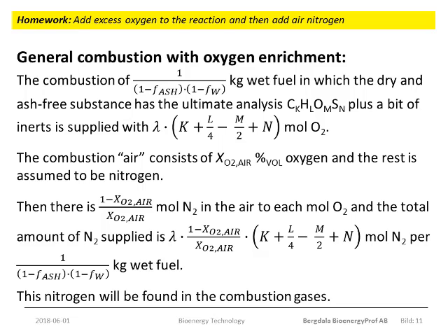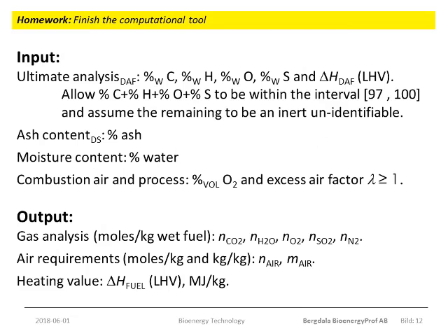Anyway, there is nothing to say that the combustion air must contain 21% oxygen. Use these equations to set up the calculation tool, and do not forget that the fuel moisture content will only be vaporized, so that the outgoing water content in the gas will be partly the incoming moisture and partly the water vapor formed by the combustion of hydrogen.